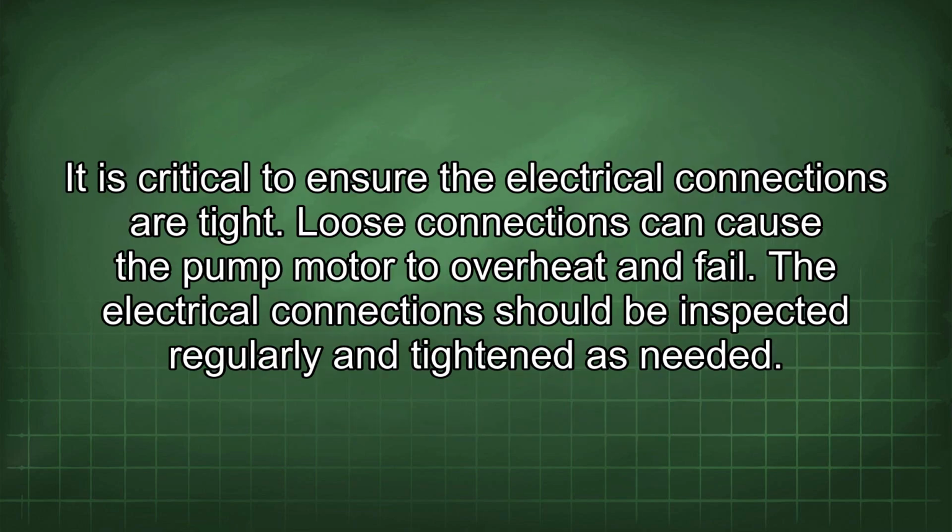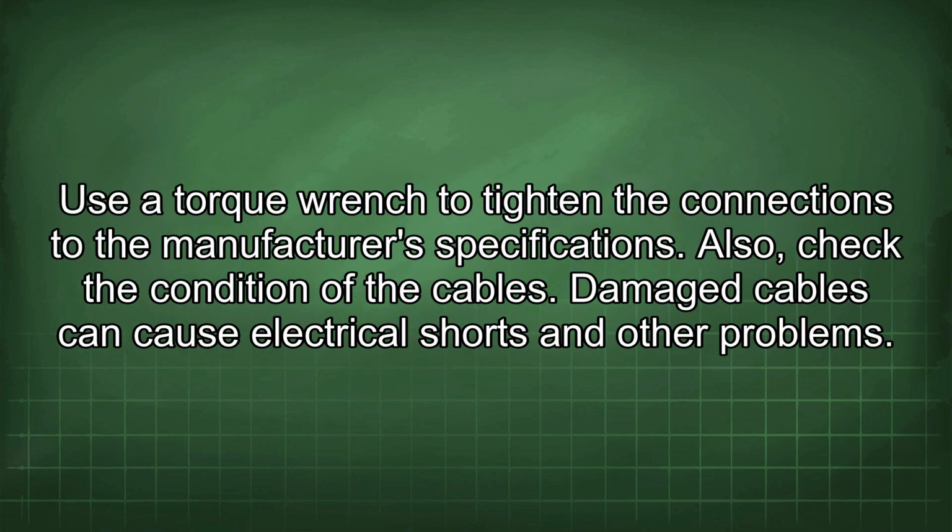It is critical to ensure the electrical connections are tight. Loose connections can cause the pump motor to overheat and fail. The electrical connections should be inspected regularly and tightened as needed. Use a torque wrench to tighten the connections to the manufacturer's specification.